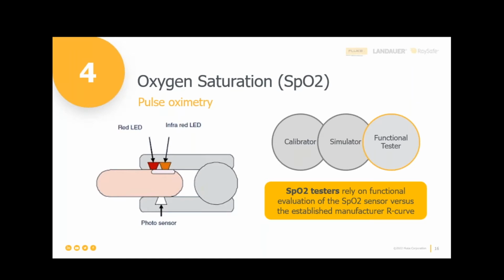We then further do more clinical studies on a bigger range of patients, comparing their O2 saturation from the about to be released or released product, medical device, in the field. And those studies and their results are combined with the breathe down studies and result in the final R curve, and that's built into the software of the oximeter that is installed in the patient monitor. And each brand and model of oximeter has typically a different R curve.